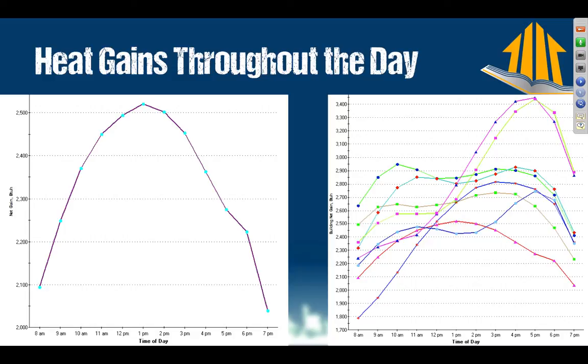Over here, you can see that there is this peak at 4 or 5 o'clock p.m. on this yellow line with purple squares and on the purple line with blue triangles. Those are parking the house so that the windows are heavily facing west. That would be bad. And in fact, that is where I'm adding 30% to my total cooling need.